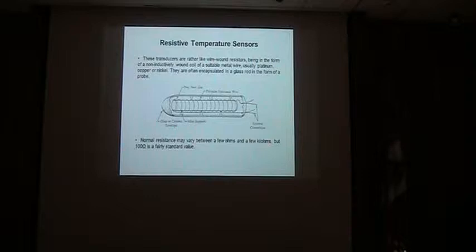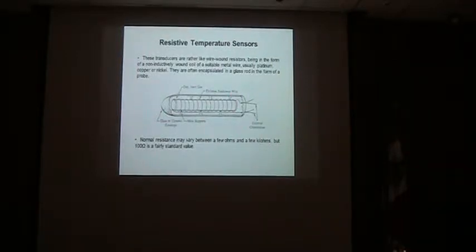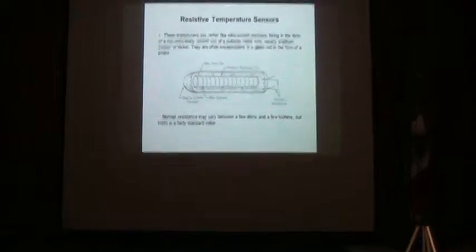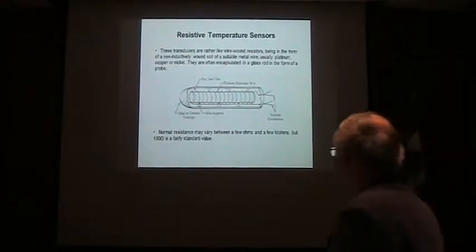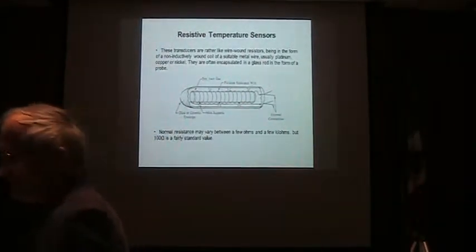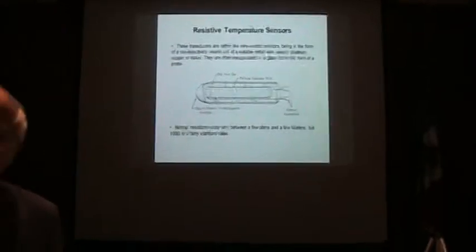Not only this. Please look that the sensing element, which is this wire wound resistor, is encapsulated. And what does it mean? That to reach thermal equilibrium, time is needed, and as a result, response and recovery time will not be very impressive.